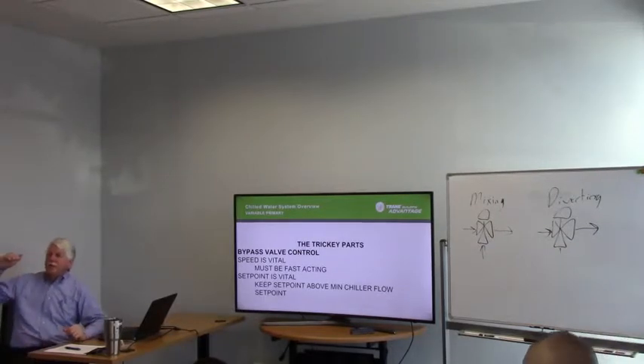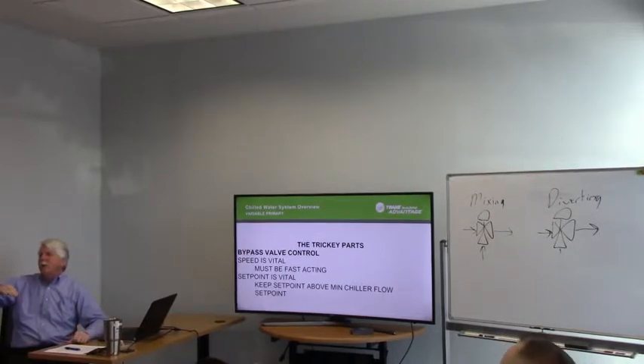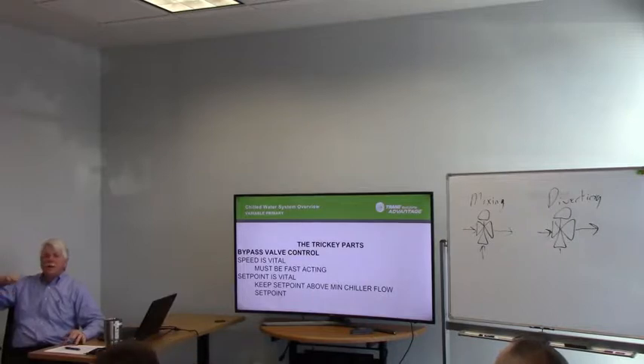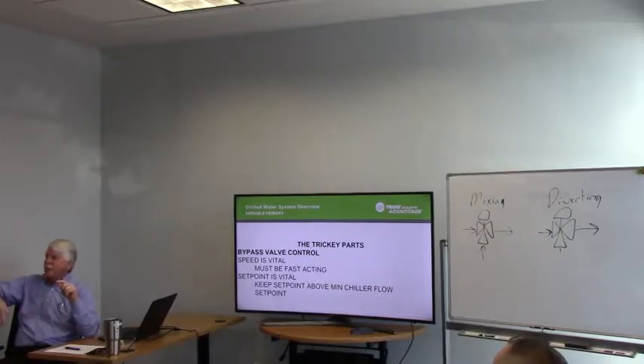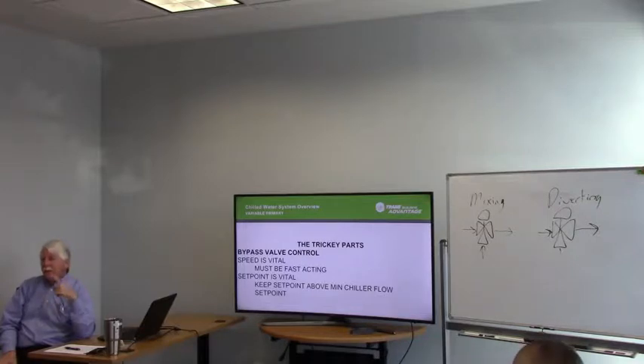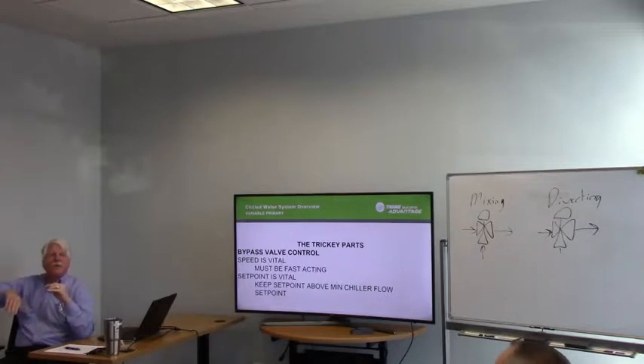We all know that we have a chiller minimum flow set point, which is usually in the catalog and on the drawings. But as we all know, if you use that set point for a DDC loop, what happens to a DDC loop? It does this, right? So if you have the set point at the minimum flow, the first time that DDC loop does this, you're going to lose the chiller. It's going to go off on minimum flow. So our rule of thumb is we will take whatever DP is required for minimum flow, and we will up that 20%. And that's what you'll usually see on your drawings for a set point. So that set point you see on your drawings is not the minimum flow for the chiller, it's the bypass valve minimum flow. And our goal is that we would never see it go below the 20% below that where we would lose the chiller.